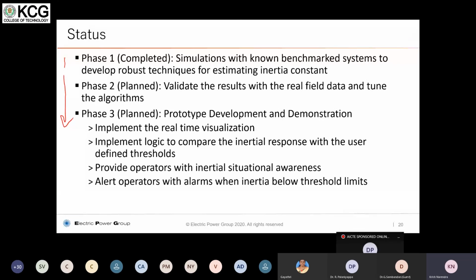Phase 2 is planned now, where we want to utilize real field data to tune the algorithms. And phase 3 is prototype development for commercial utilization, to implement the real-time visualization and the logic of the system, to provide operators with inertial situational awareness. For example, today, if you use synchrophasor data, situational awareness comes from measurement of the phase angle of the system, because in bulk AC power systems the phase angle is directly related to the stress in your transmission system.